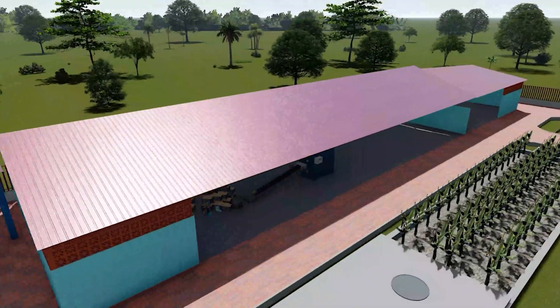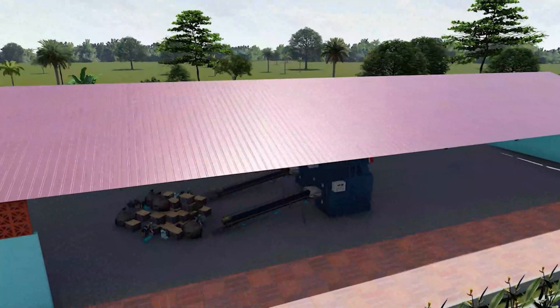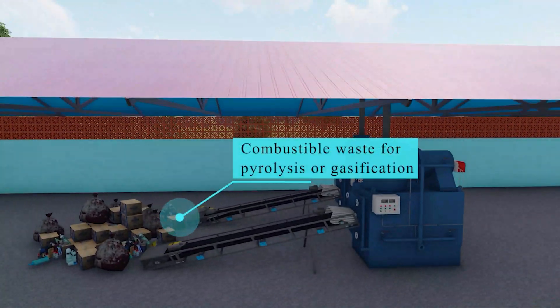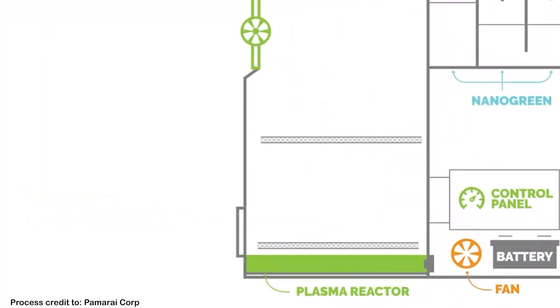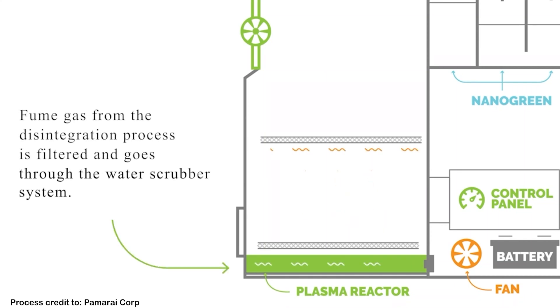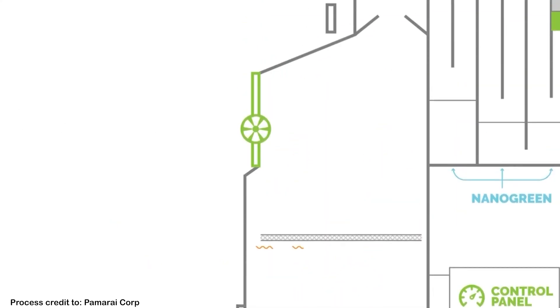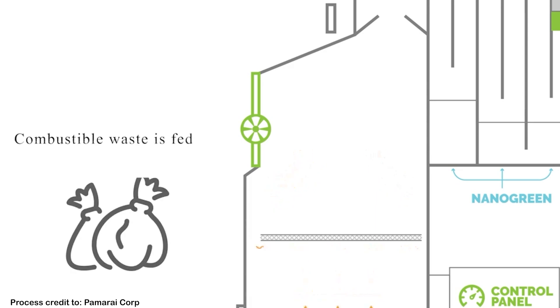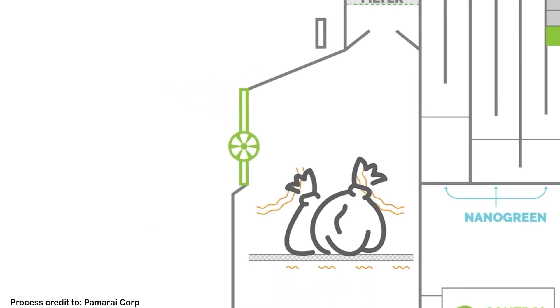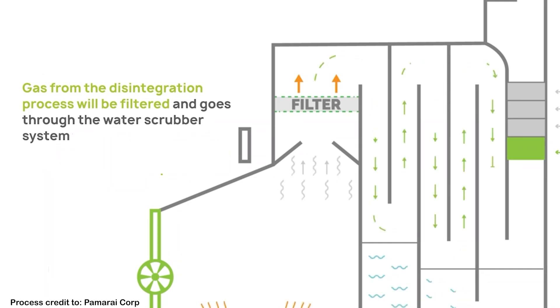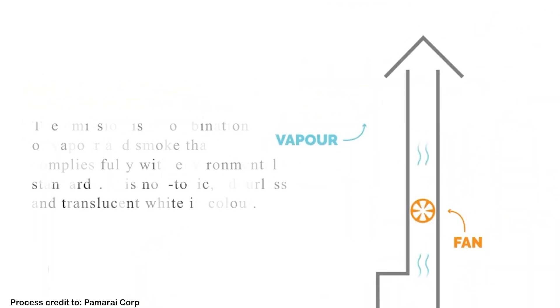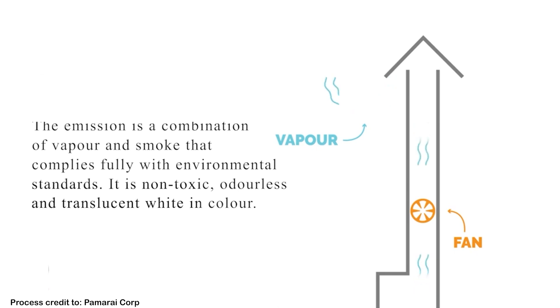For combustible waste, a state-of-the-art plasma gasification unit is employed. Utilizing a controlled gasification process, this unit converts combustible waste into gaseous constituents and an environmentally compliant incombustible residue. The generated gases undergo a series of cleaning processes, including cooling, scrubbing, and cyclone separation, to produce clean gas that meets atmospheric release standards.